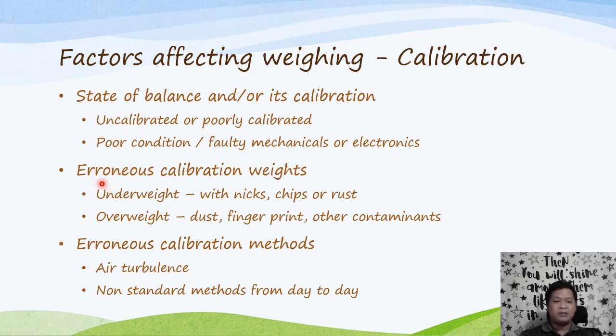Also, calibration weights could be erroneous, no? So over time, pag nabagsak siya, natatapyasan yung bakal, or kinakalawang siya, or usually these weights are handled with tongs because fingerprints and other contaminants might make the calibration off dahil nagsisettle yung dust doon or what, or moisture. Okay, and then pagdating naman sa method mo, you could also encounter air turbulence. Kaya nga yung mga analytical balances especially, meron silang sariling glass cabinet, no? Kasi kung mapapansin nyo kung sa lab, nakatutok yung electric fan habang nag-weigh ka sa analytical balance, hindi nag-stabilize yung reading ng balance mo kasi yung effect ng air, may downward force siya, nare-read yung balance mo kasi ganun siya ka-sensitive.